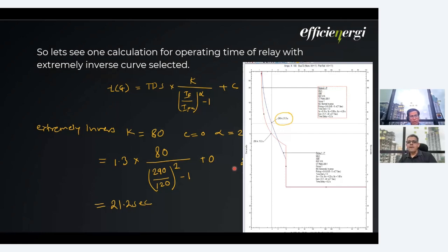Okay. So again, these are the theoretical values, because here you will see there is no maximum or minimum specified in this curve, because the relay only gives the tripping signal. The tripping has to be carried out by the auxiliary relays and the circuit breakers. And there is no fixed combination of a relay and a circuit breaker. If there is a fixed combination, then we can define maximum and minimum. But relays can be used with any combination of auxiliary relays as well as breakers. So here we only get this kind of curves.